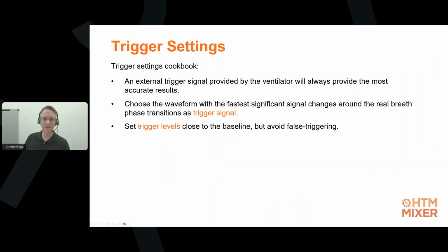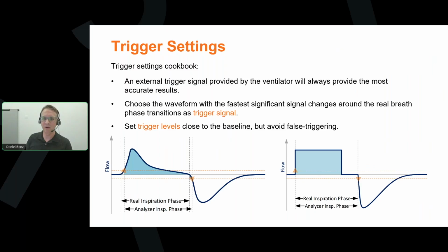For the trigger levels, meaning the threshold level for the trigger, it's always a bit of a trade-off. On one hand, we want to get as close as possible to the signal baseline to capture the start of the breath phase as accurately as possible, because the more delayed we are, the more inaccurate our breath phase parameter measurements are going to be. We've seen that in our earlier example.